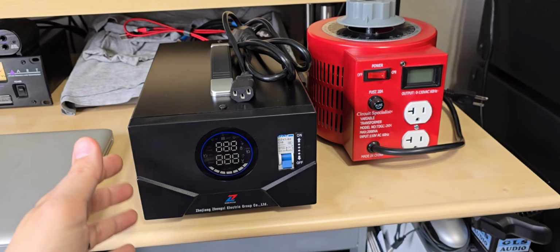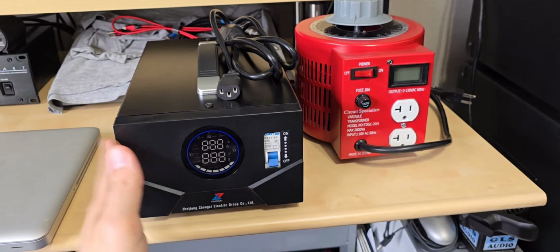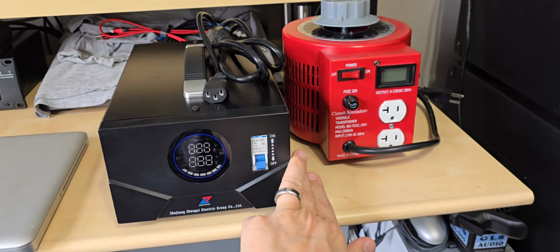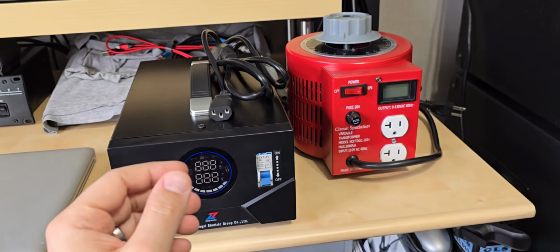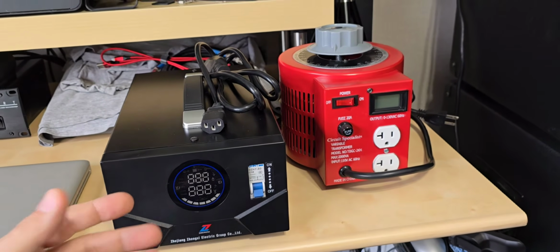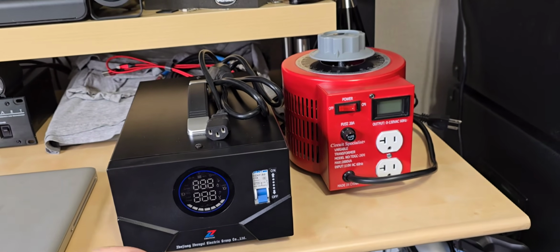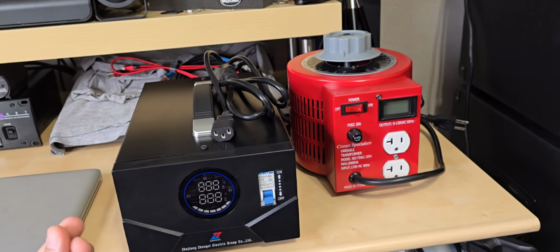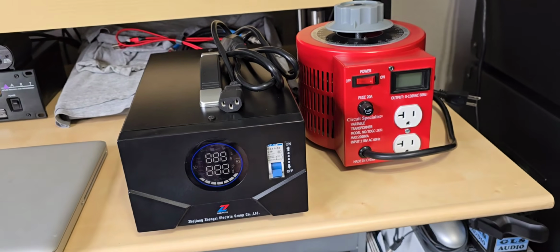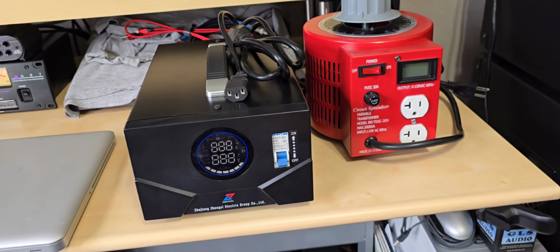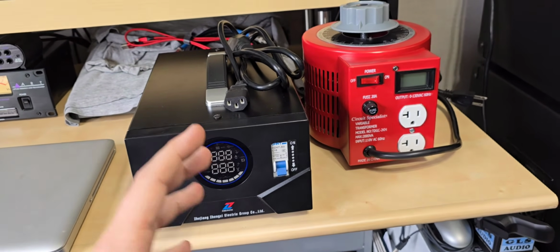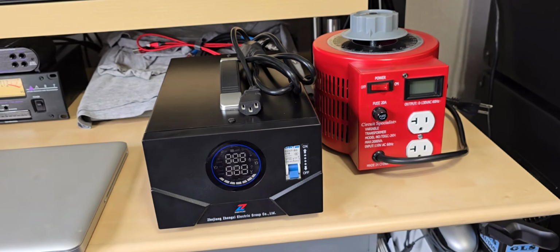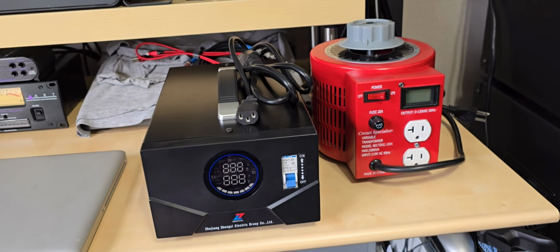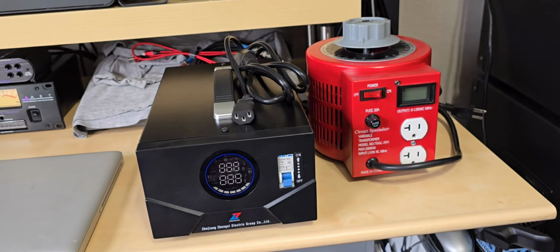Now, lower frequencies: 60 hertz is what we want. We want 60 hertz to go in, we want 60 hertz to come out, but you also have to deal with the harmonic distortion, so the harmonics of 60 hertz, so 120, double that, 240, and so on and so forth. Those are the frequencies that we don't want. And the slower the frequency, the bigger the transformer needs to be, or in this case, an inductor, which is essentially acting in the same manner.